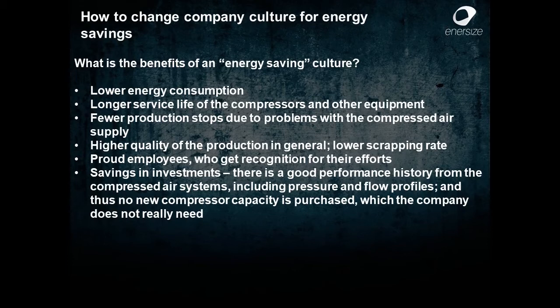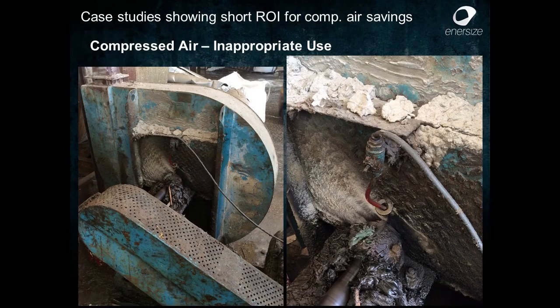We'll skip to a few, what I call, compressed air classics. The next few slides are pictures of what I mean by inappropriate use of compressed air. Here you see an ordinary fan that is producing combustion air for a boiler system. And this wire you can see going to the bearings is actually compressed air, an open pipe that blows compressed air down to the shaft and the bearings to cool down the bearings and the fan system. This is not the way you should do it, and it is an extremely expensive way to cool down bearings. I would recommend that you fix the bearings instead.